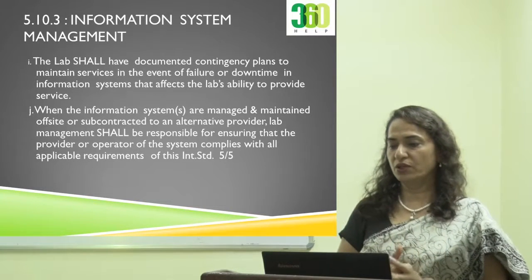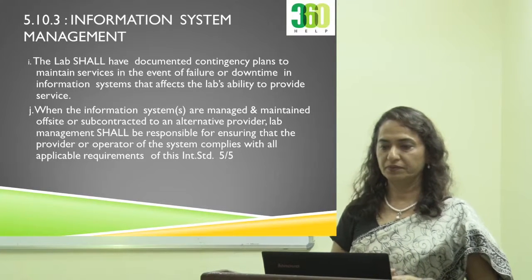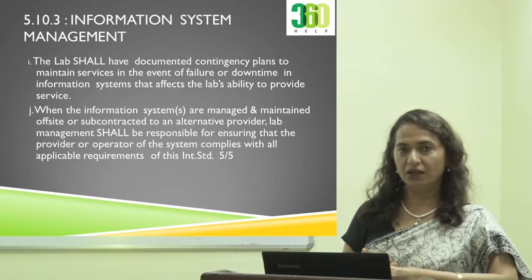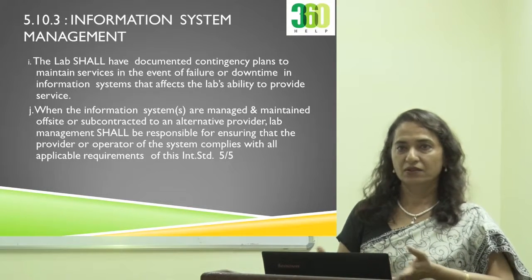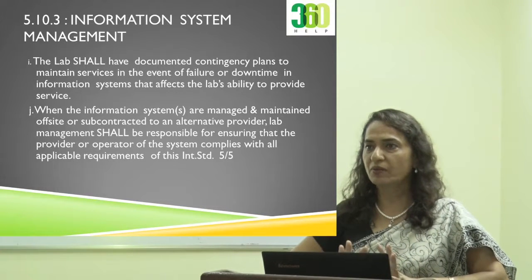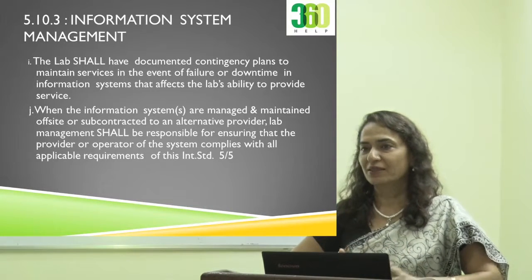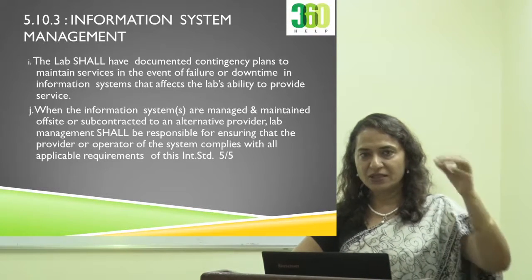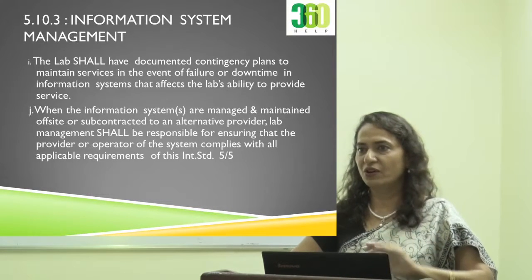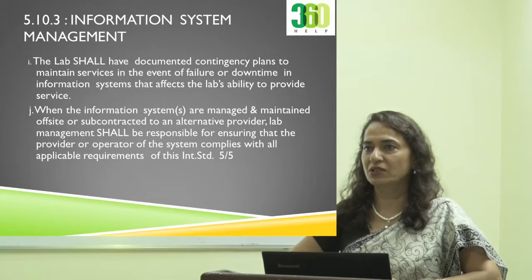Then data storage. This once happened with us. What happened? I was telling my friend, a rat bit the cable, and in the morning we saw it was not working. What to do? It's a big problem. Back up the system manually. It's a very big problem, and it happens in almost every other lab once in a while, because the tubings have serum in them, so rodents are very fond of cutting those. This happens, so you have to be careful about all these systems.